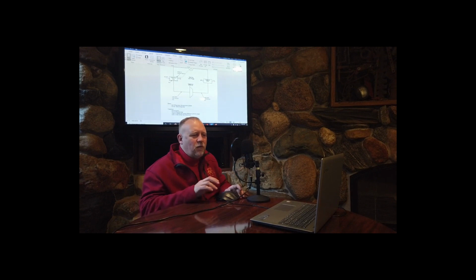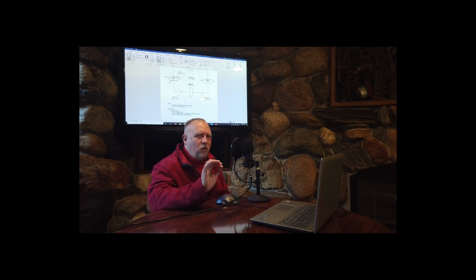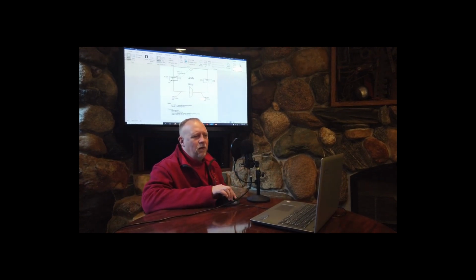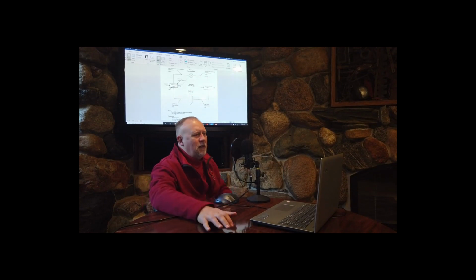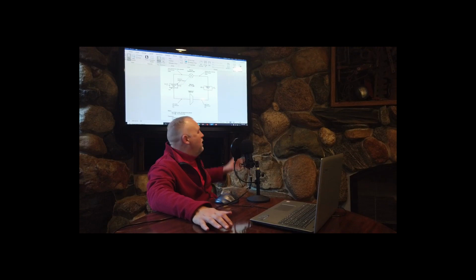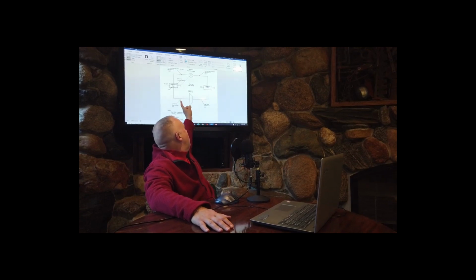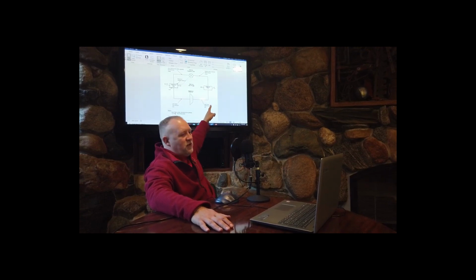Okay, so let's recap here. Most of the energy consumed by this process is consumed in the compressor. The compressor causes the increase in pressure from the low pressure side to the high pressure side. This has to be a gas, a vapor coming into it.